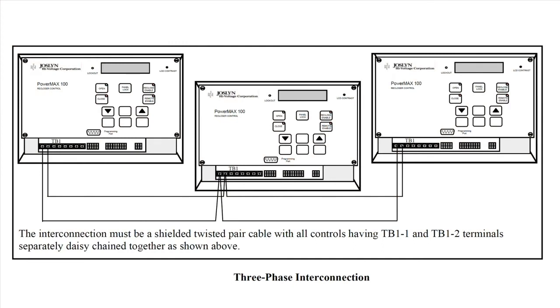Three-phase lockout. Three-phase or ganged lockout allows PowerMax controls to be connected together so that if one control goes to lockout, the other connected controls will open their respective tri-mod recloser. When PowerMax controls are connected together, each individual control and tri-mod recloser operates based on its own pre-programmed settings. Therefore, when each system clears a temporary fault, the other phase or phases are unaffected because only that tri-mod recloser will open and reclose. If the fault is permanent, the PowerMax on the particular phase will go to lockout and issue a command for the other connected PowerMax controls to open.